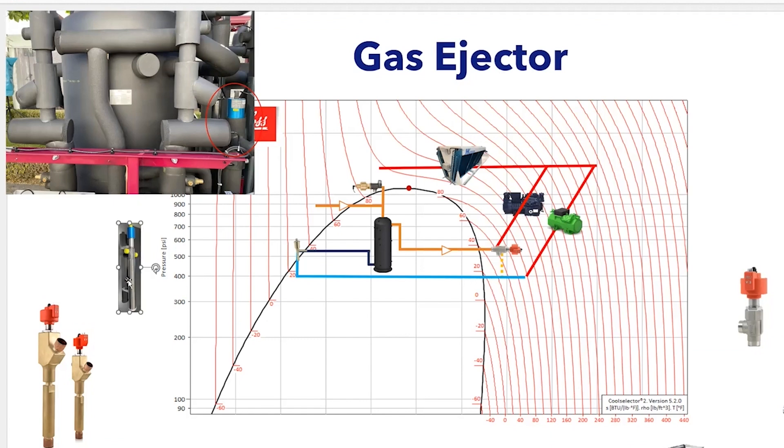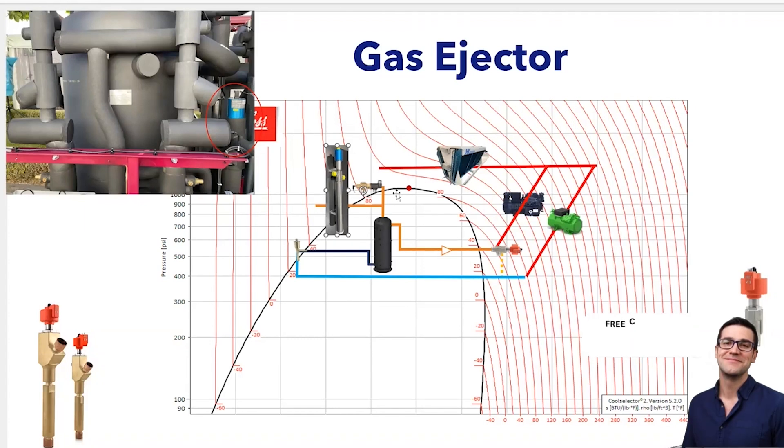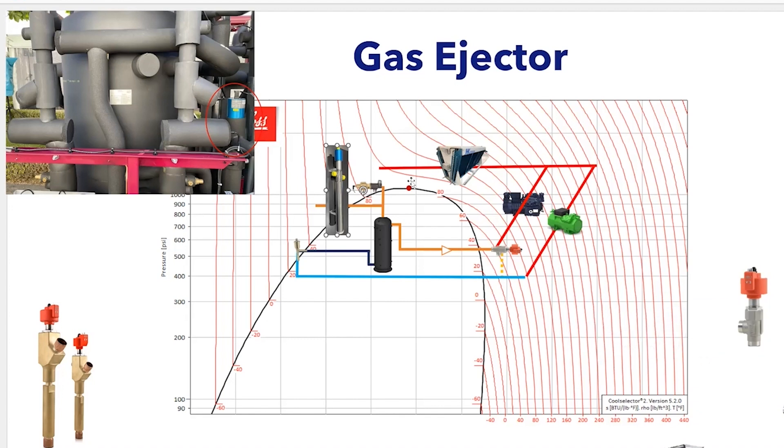Where the ejector comes in now, instead of going through your high pressure valve, this ejector is actually acting as your high pressure valve. In theory, you don't need a high pressure valve, but most manufacturers will have an ejector valve in parallel with another high pressure valve. When that ejector valve maxes out, it'll move over to the high pressure valve.